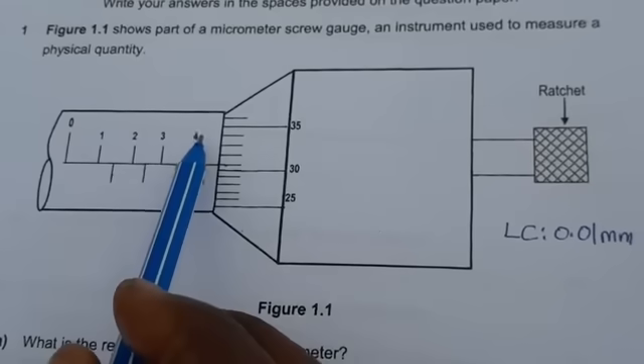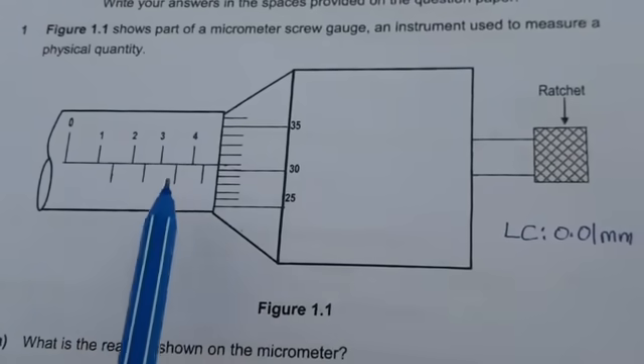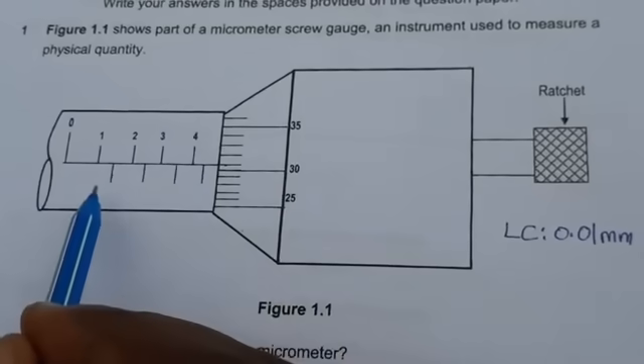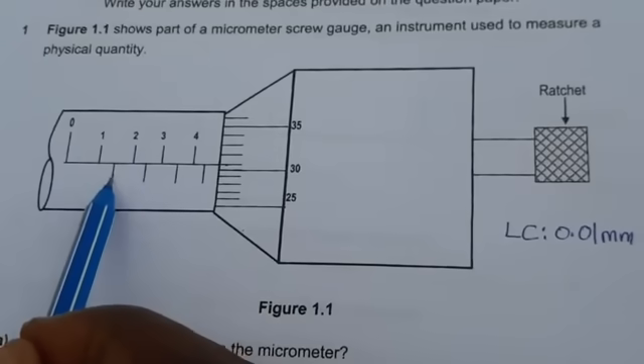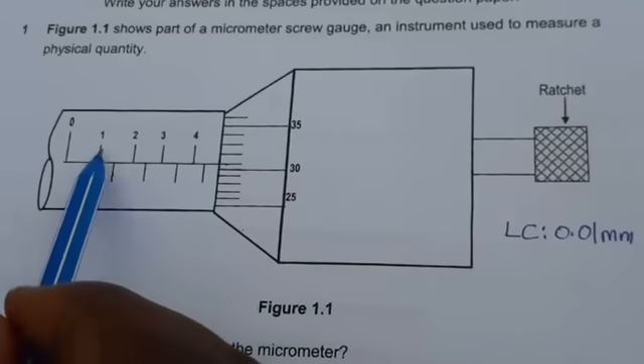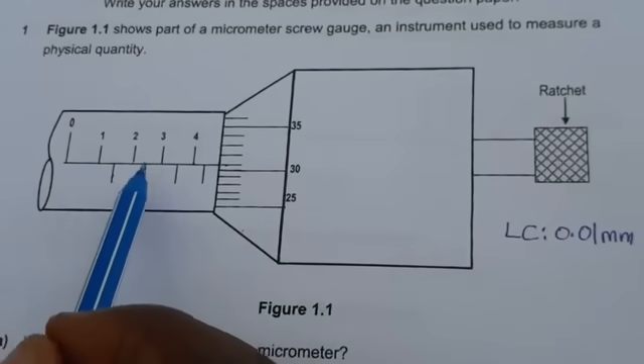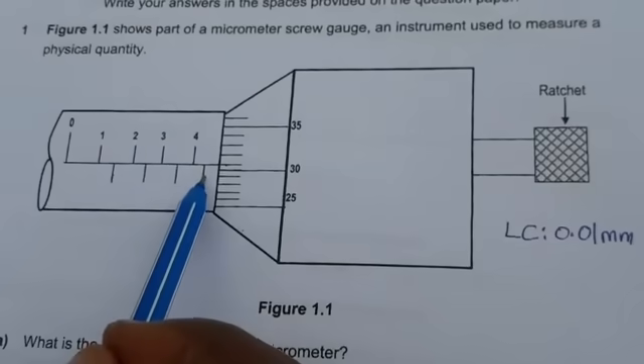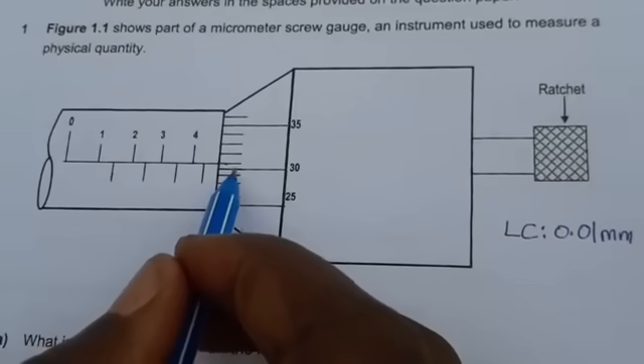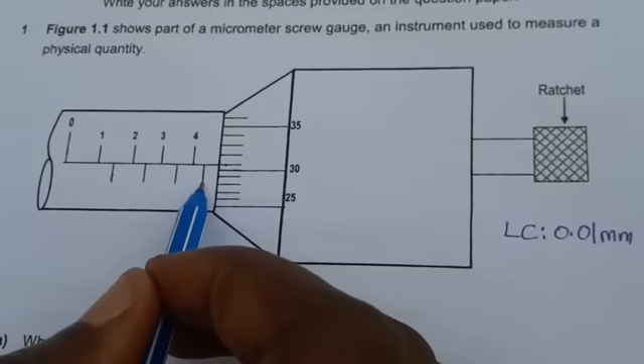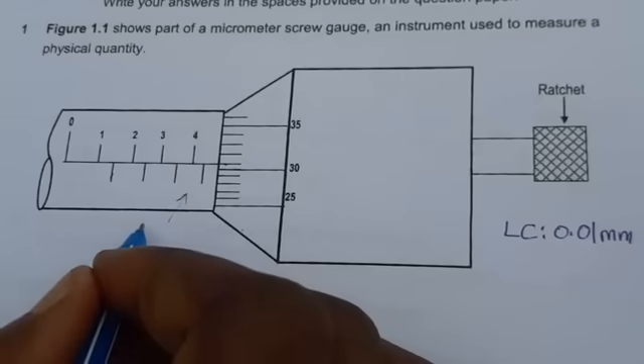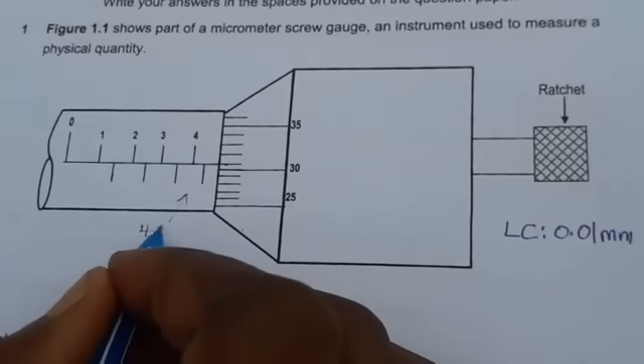This instrument is in millimeters. We have 0, 1, 2, 3, 4 millimeters on the sleeve reading. The first thing we're going to do is take the measurements of the sleeve scale. We have 0, then 1. This demarcation or graduation that is down here indicates the 0.5. So we have 0, 1, 0.5, 2, 0.5, 3, 0.5, 4, 0.5. This is the last measurement before we go to the thimble reading. So this sleeve reading is 4.5 millimeters.